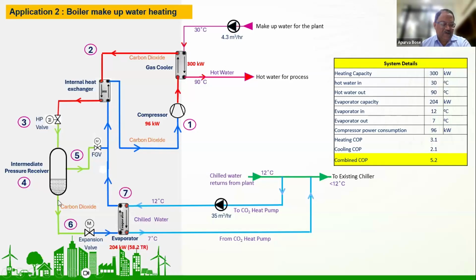Now this liquid one comes down at 50 bar pressure and goes through the expansion valve here, and after that expansion, it becomes 38 bar and 3 degrees Celsius. This serves the chilled water, whose return temperature is coming at 12 degrees Celsius. Now this can make it 7 degrees Celsius. We can provide it at 7 degrees Celsius. So obviously it reduces the load on the existing chiller, as I was mentioning earlier. And this CO2, after the expansion valve, goes through this evaporator, through the IHX, the internal heat exchanger, and goes back to the compressor. So this is how the loop gets completed. It is a closed loop application.